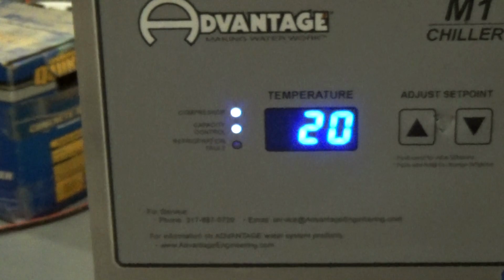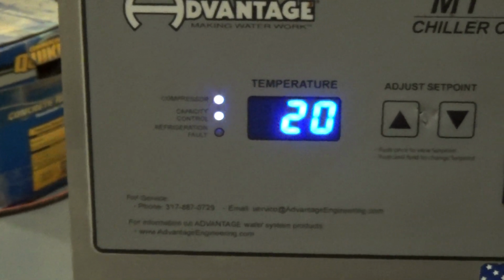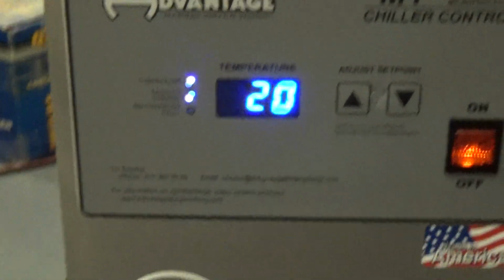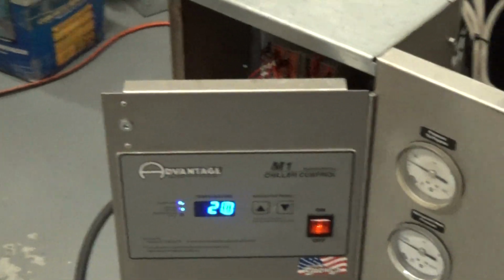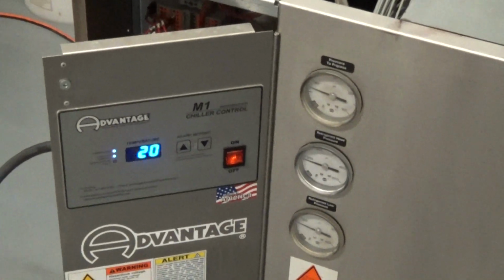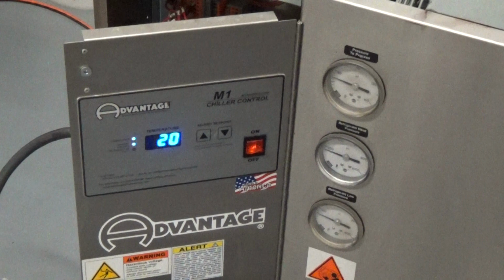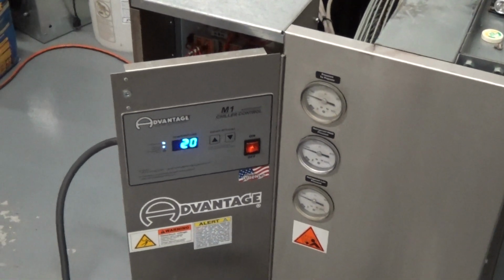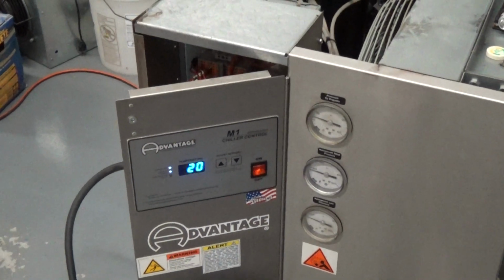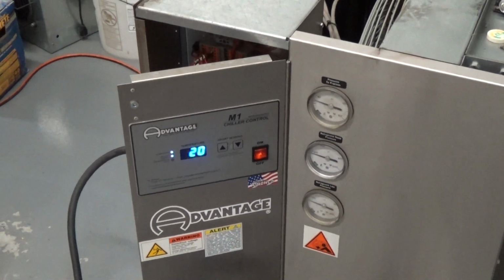Second lower light there. Let's see if that's legible. But focus? Oh, it's not focusing. The top one says compressor, the second one says capacity control. The bottom light is refrigerant fault. When that comes on, it doesn't always necessarily mean it's a refrigerant fault. It could be something else that creates the refrigerant fault. For example, if you didn't have enough flow going through the heat exchanger coming back to the chiller, that'll create a low flow and, because of the low heat transfer, a refrigerant fault.